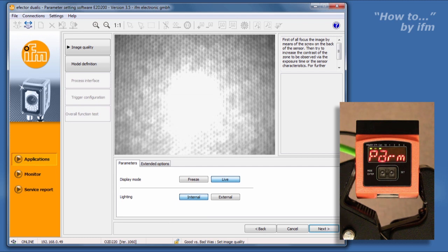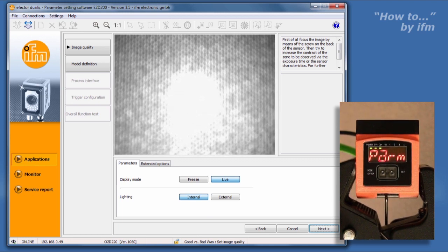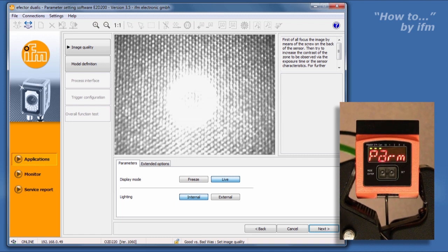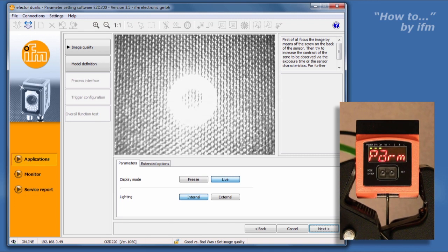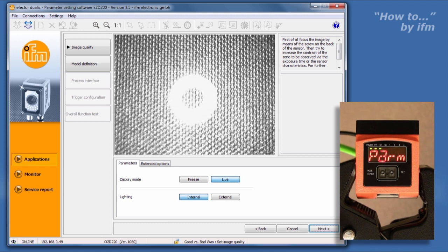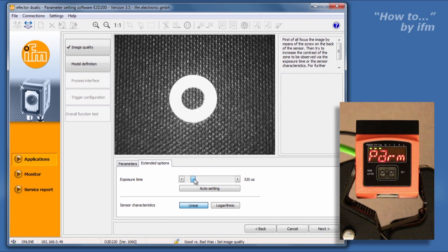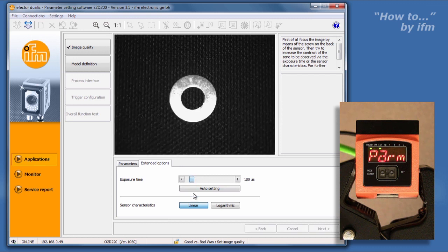The first step in adjusting the image will be to focus the camera. With a target object placed within view of the O2D, use the supplied screwdriver to turn the screw on the back panel of the O2D housing, bringing the object into focus. In the image quality screen, select Extended Options. In this example, the image is a bit too bright, meaning the exposure time is too high. This can be easily adjusted with the exposure time slider.